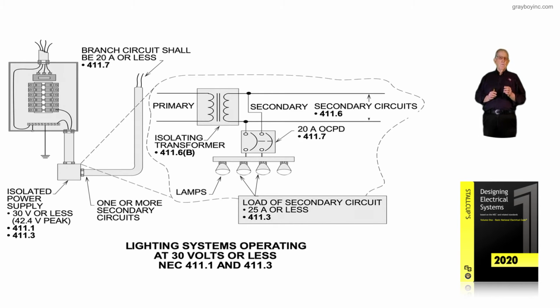And of course, we can have one or more circuits coming off of that isolation transformer. But with the isolation transformer, there's no way anyone's going to get shocked from it. We're not to ground it in any way. But notice the load of the secondary circuit is limited to 25 amps or less in accordance with 411.3, as shown in the boxed in information.